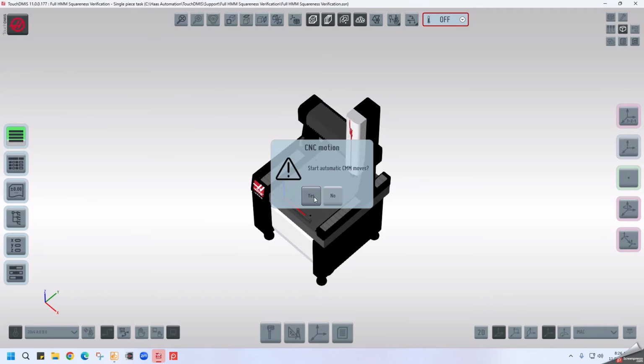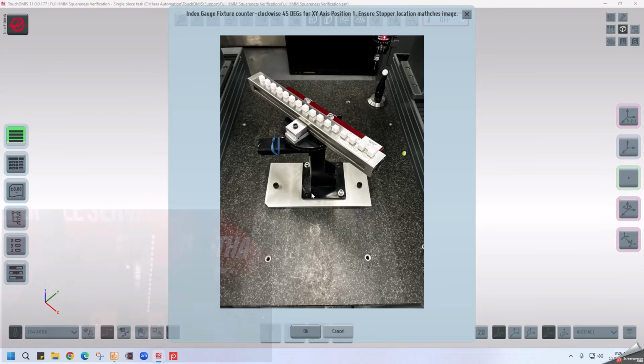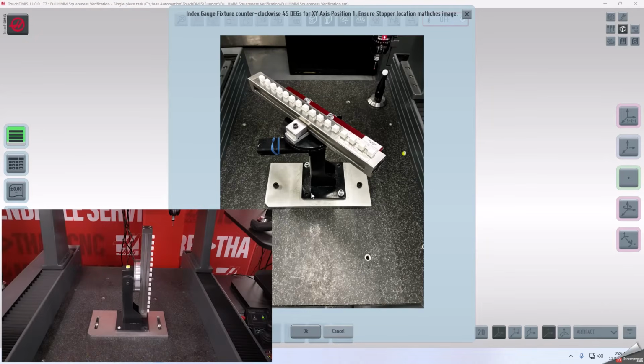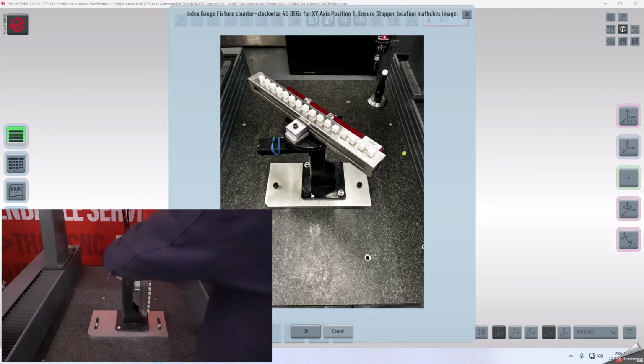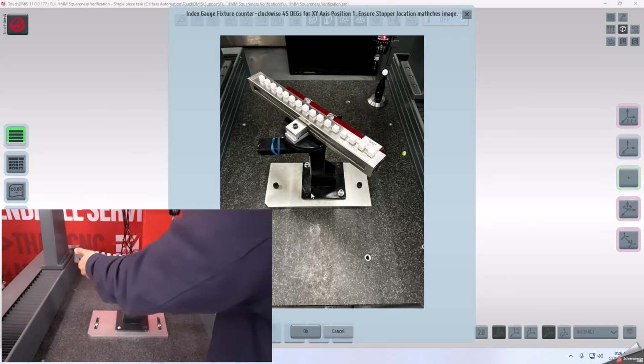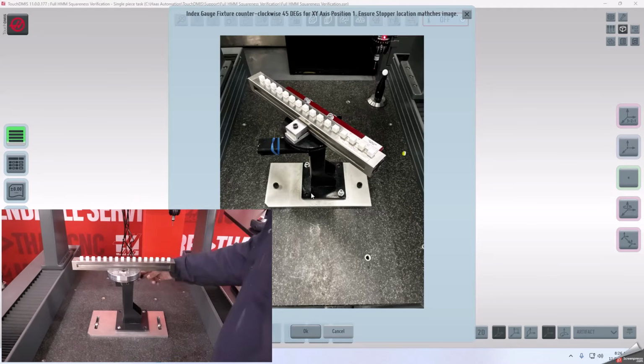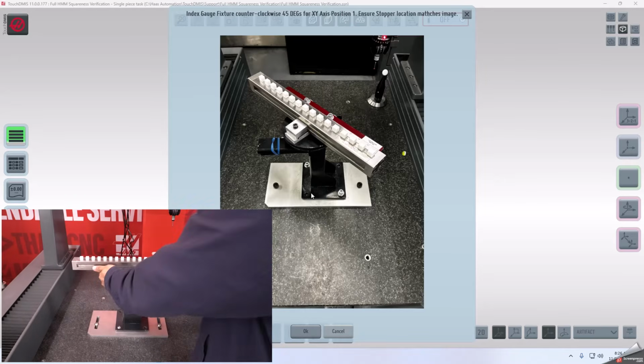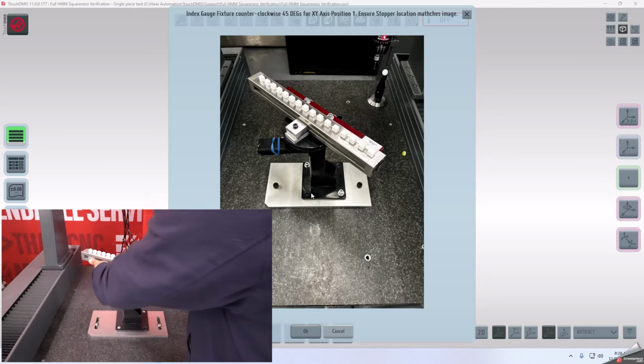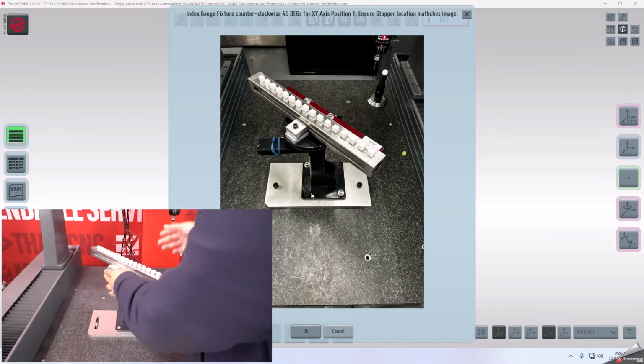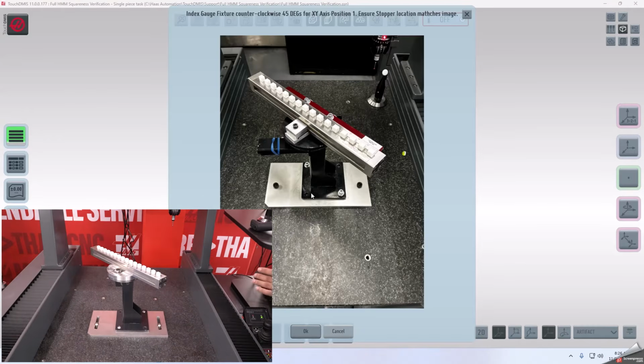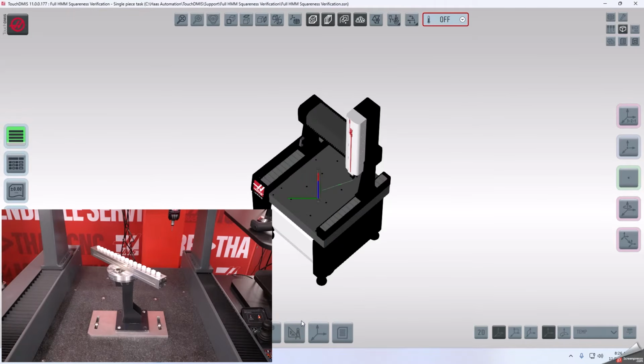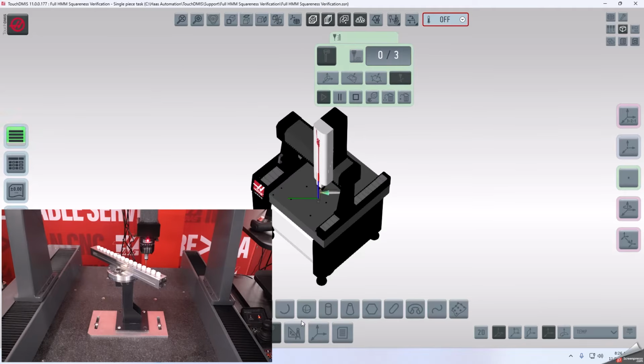Then I'll select yes to start the automatic CMM moves. Now the first thing I need to do is unlock the latch on the fixture. Then I'll tilt the step gauge back to its original position. Then I'll lock the latch. And I'll rotate the step gauge 45 degrees to the right. One click. Now I want to make sure that my step gauge on the HMM matches the orientation on the image, then I will select OK. Now the HMM will automatically align the step gauge and perform its measurement routine along the XY axis.